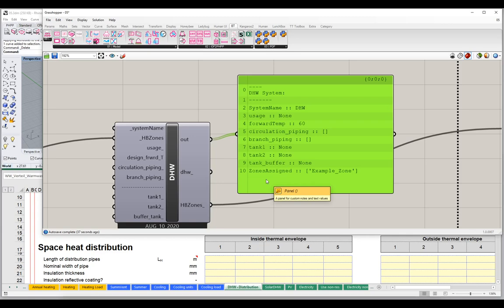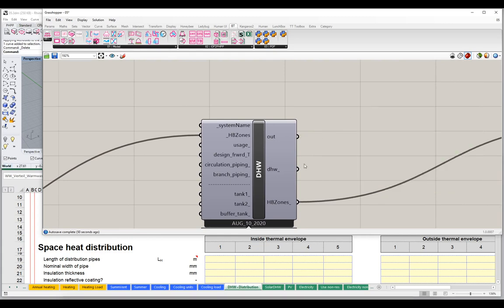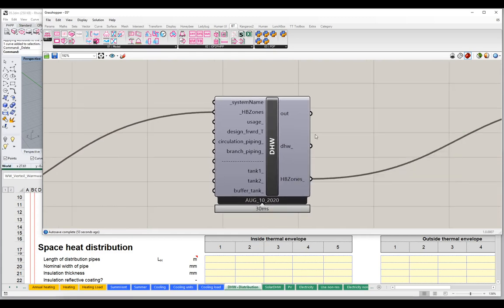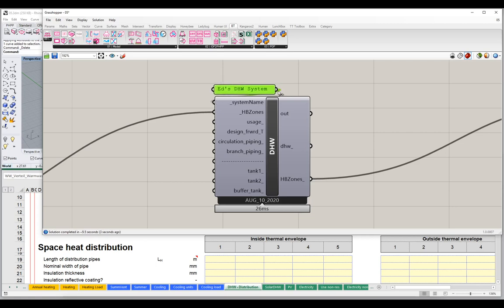Our next step is to start adding some information. Let me give this a name — I'll call this 'domestic hot water system.' Maybe you would call it 'first floor system,' 'residential tower system,' or 'commercial podium system' — you want to give it a unique name for this to work properly. So that's all working properly now. We could choose to input a usage profile, a different design forward temperature to override the default 60 degrees Celsius, and we have options to input circulation piping, branch piping, and domestic hot water tanks — as well as a buffer tank for solar thermal.